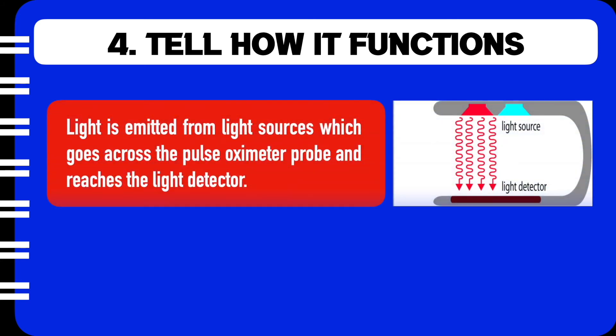Coming to the last part of a description, in this we are going to talk about how the oximeter functions. Now light is emitted from light sources which goes across the pulse oximeter probe and reaches the light detector which you can see at the bottom.